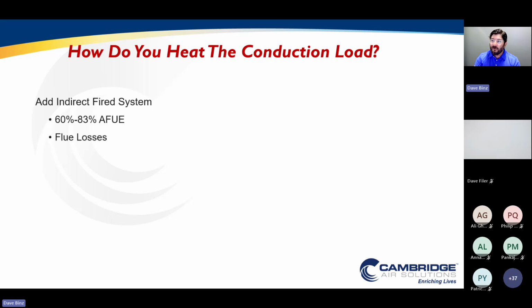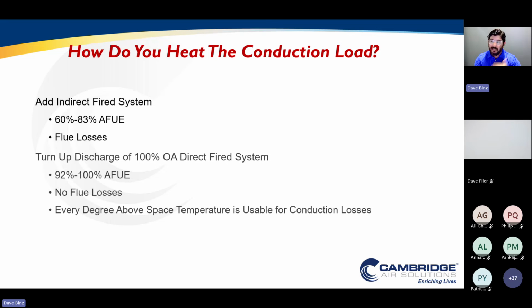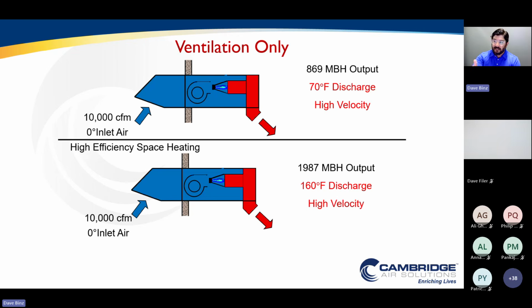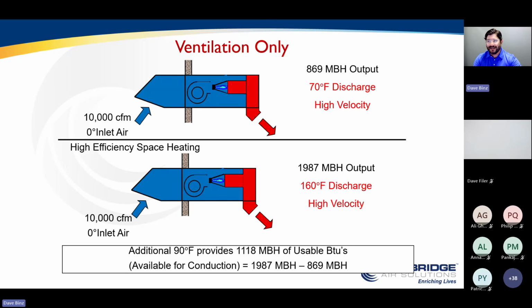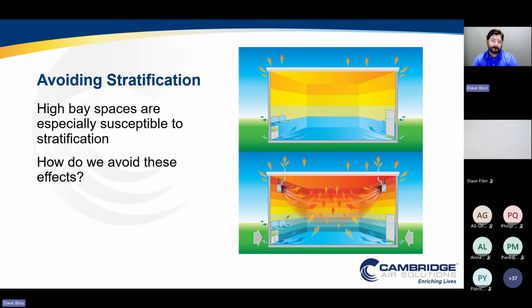But what does HTHV do? Now, instead of adding other recirculation space heating systems like package rooftops, unit heaters, or any other gas-fired or heat exchanger style heating source that has flue losses, I can just use my ventilation system and increase my discharge temperature. I get a lot more heat to offset other losses, whether that's skin losses or additional variable infiltration losses. So it takes that 10,000 CFM makeup air unit and turns it into a 10,000 CFM industrial space heater and ventilation unit that can do my ventilation needs and have over 1.1 million BTUs of usable heat for skin losses, conduction losses, or variable infiltration around the perimeter and my dock doors. That's the core of the heating side of the HTHV.